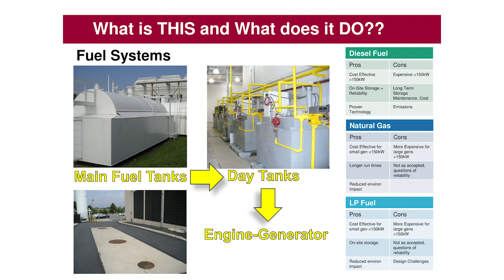On the fuel side, we'll usually have a main fuel tank, whether above ground or underground, that feeds smaller day tanks, usually closer to the generator, holding about 3 hours worth of fuel. From there, fuel goes to the generator. You see a lot of exterior generators in weatherproof enclosures with a belly tank or skid-mounted tank right under the generator, same thing as a main tank. You don't usually need a day tank because it's right there. But we're going to talk a lot about fuel systems, probably more than you want to.